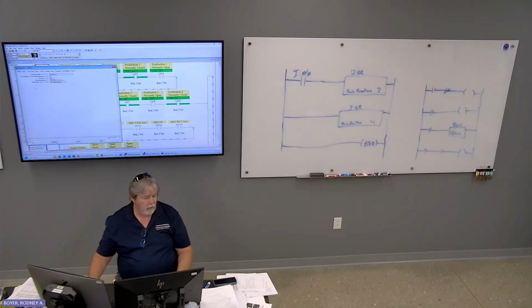So, processor mode. Word 1 bit 0 through word 1 bit 4 will tell you what mode it's in. Last time this program was saved, the controller was in remote run mode. On power up, go to run mode behavior: you can set your program so that when the controller first powers up, you can prevent it from jumping straight into run mode, which is what it would normally do. I can't think of any good use case scenarios for that. If you program your system correctly, you don't need that kind of feature.